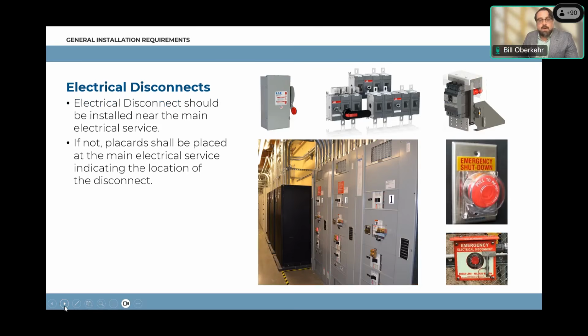Got a little bit more on disconnects here. This is mostly just to show you what they might look like. It's not always a button. Sometimes we have the knife edge. There are different types, but they should be labeled. Signage requirements require that they are. So the point of these, again, is to make them readily accessible and identifiable by emergency responders in the event of emergency. Can we go to the next slide, please?